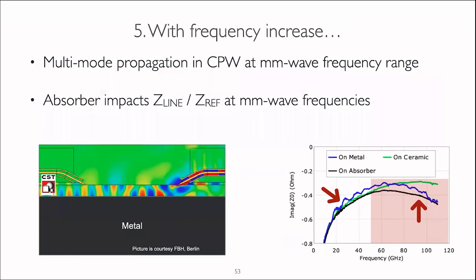With the frequency increase into the millimeter-wave ranges, we actually have a couple of other problems that we need to deal with. In particular, this is multimode propagation. Coplanar waveguide structures, like a traditional calibration substrate, support higher-order modes in the coplanar waveguide, the transmission lines and standards, if they rest on the metal chuck. This picture shows the electromagnetic wave structure at 110 gigahertz when the calibration substrate is placed on the metal chuck. What you can see here is that the waves are completely distorted because they are the result of the superposition of different modes, and higher modes are not desired for the calibration.